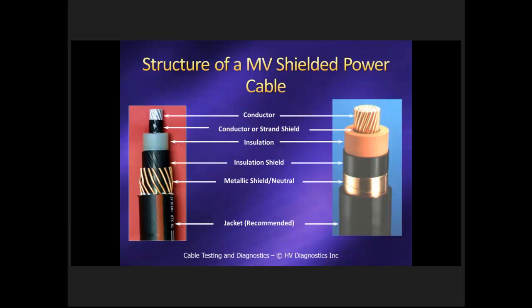That is covered by an outside insulation shield, which again forms the purpose of creating a very smooth interface between the copper concentric neutral cables, as you can see on the left, or the tape shield copper that you can see on the right. So any sharp points that may be on those two metallic elements don't become sharp points that get directly attached to the insulation. That could cause partial discharge and breakdown of the insulation. In both cases, on these pictures, you can see a jacket. Not all cables out there are jacketed. There's quite a lot of unjacketed cables too, again, particularly in the distribution area.